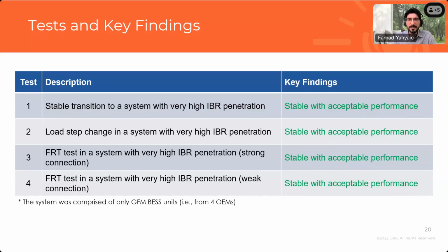I want to emphasize that for the models used in this study, we tried not to perform any model tuning or change parameters. The inverter and controller parameters are mostly the default ones provided by the OEM. We did adjust some droop settings at a high level on the plant-level controller to get similar steady-state behavior, but dynamically, all the gains and controller parameters remain the OEM defaults.